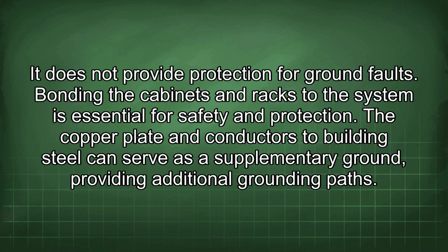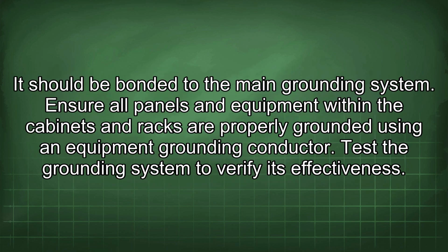The copper plate and conductors to building steel can serve as a supplementary ground, providing additional grounding paths. It should be bonded to the main grounding system. Ensure all panels and equipment within the cabinets and racks are properly grounded using an equipment grounding conductor. Test the grounding system to verify its effectiveness.